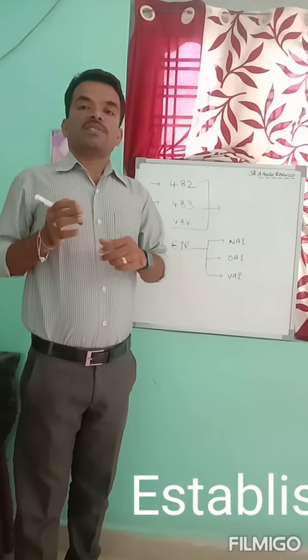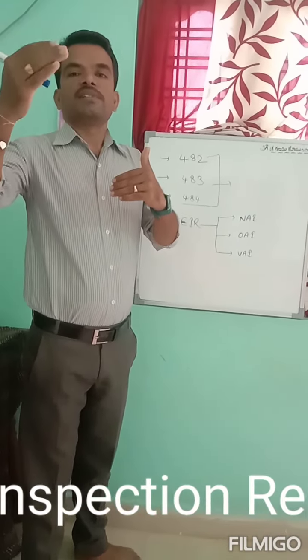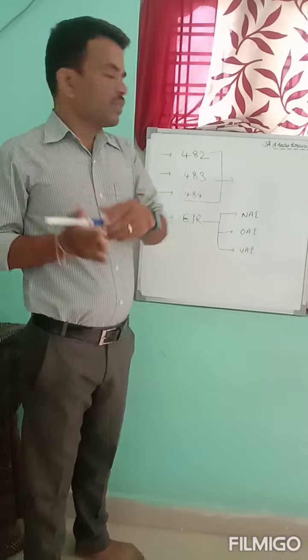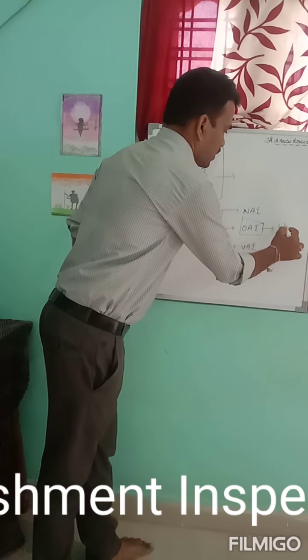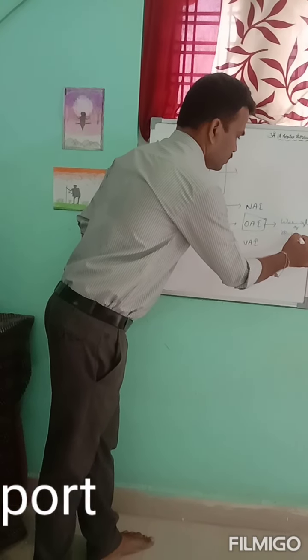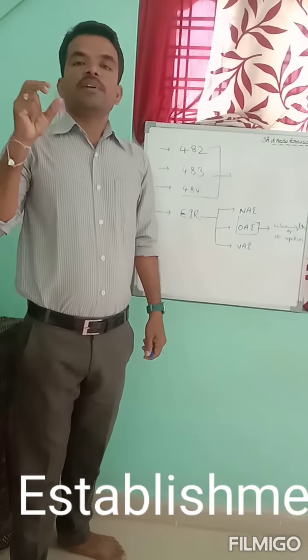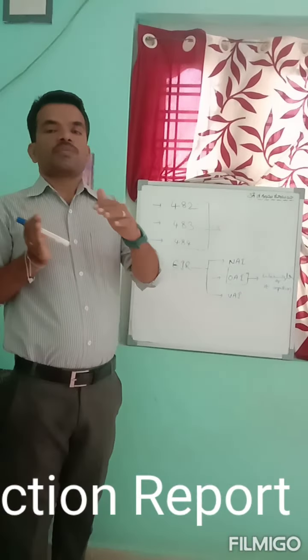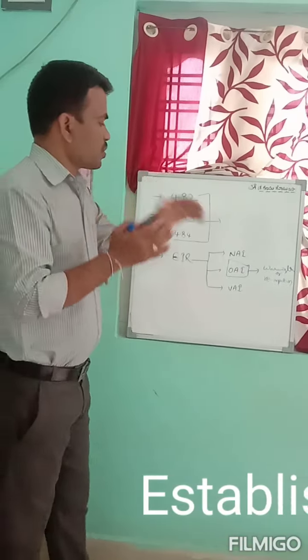OAI means Official Action Indicated. This means they are not satisfied with the observations found and the responses are not acceptable. Based on that, they will give an OAI — Official Action Indicated — and based on this they will issue warning letters or a re-inspection schedule. When they find abnormalities and are not satisfied, they will issue the 483 form. If the observations are not resolved, they will issue a warning letter, and if still not satisfied, there is a chance to revisit and re-inspect the site.